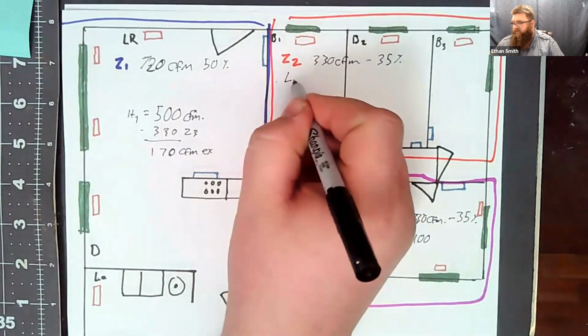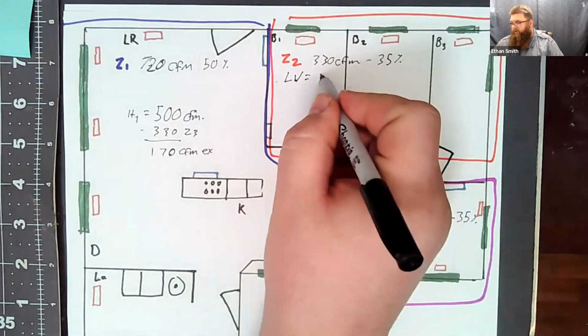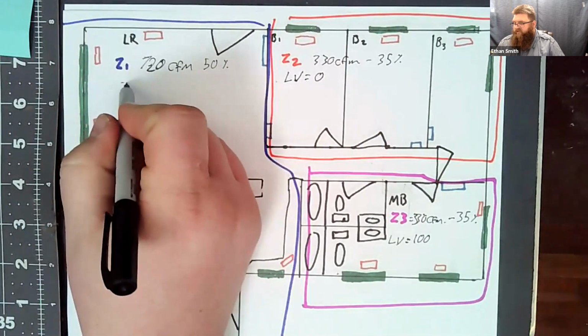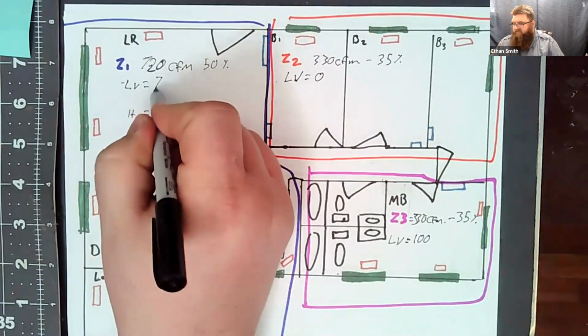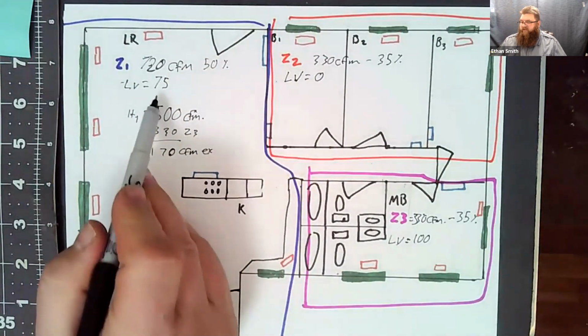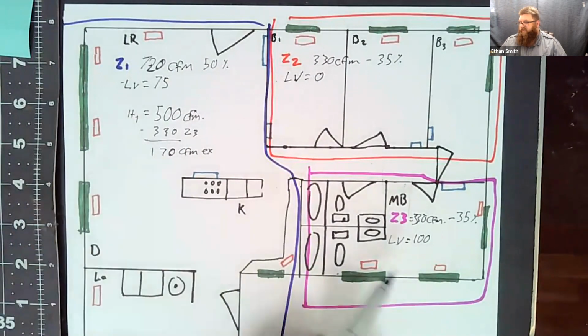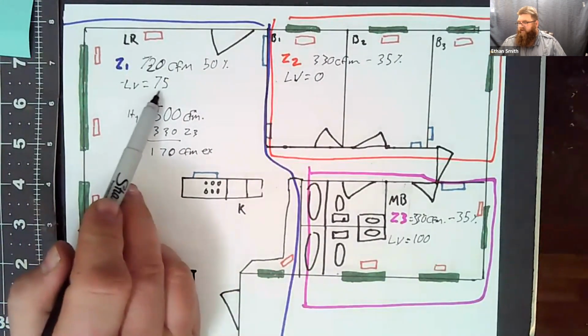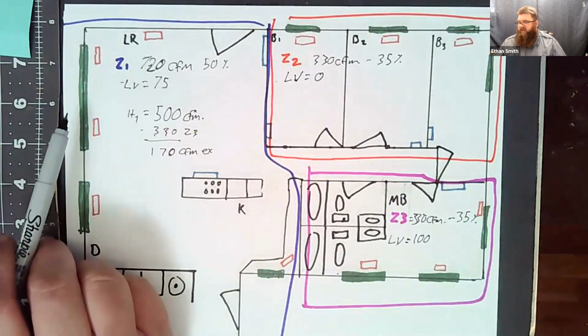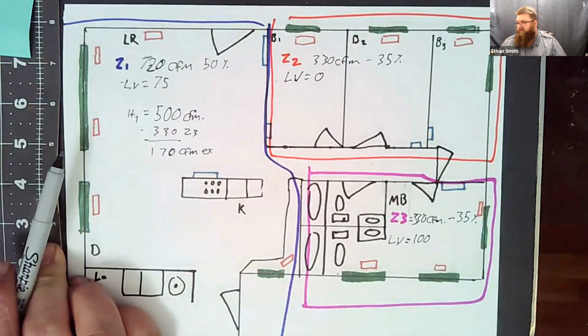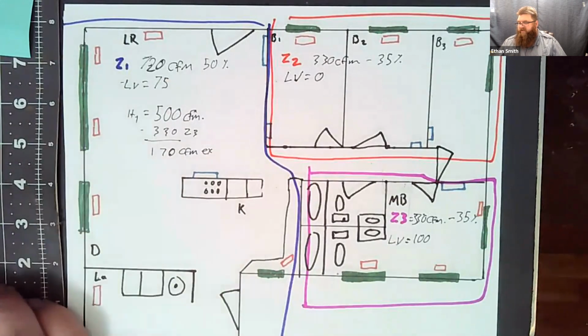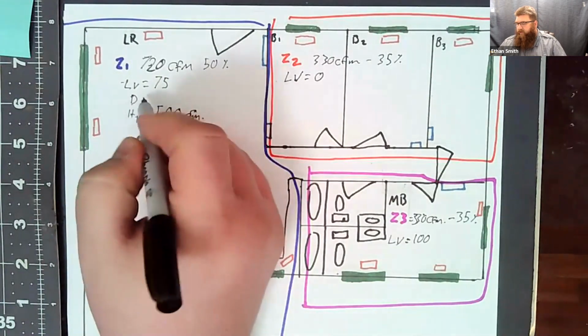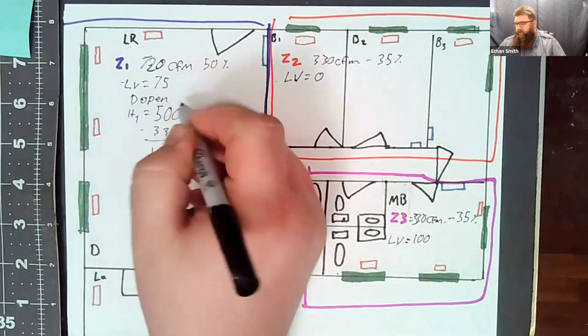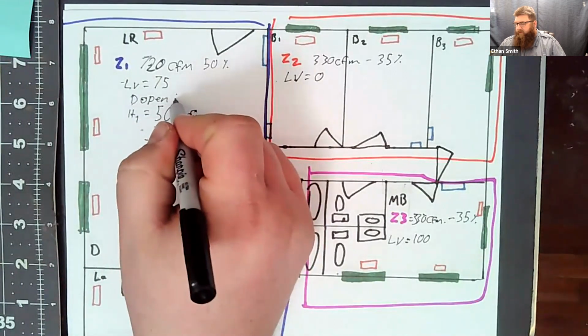So we can look at the load value for zone 2. We look at that one, let's say it reads 0. And we can look at the load value for zone 1 and say it's maybe 75. So it hasn't reached 100 yet, so it hasn't called for the equipment, but my system can see that I've got a zone that's creeping up to the point where it's going to need to get some heat into that zone. And so what we can do is what's called intelligent relief. This pairs up with modulating dampers. So we have power open, power closed dampers so that we can control the position of them. And we're able to actually take this damper and open it to its minimum position, which would be 25% open.